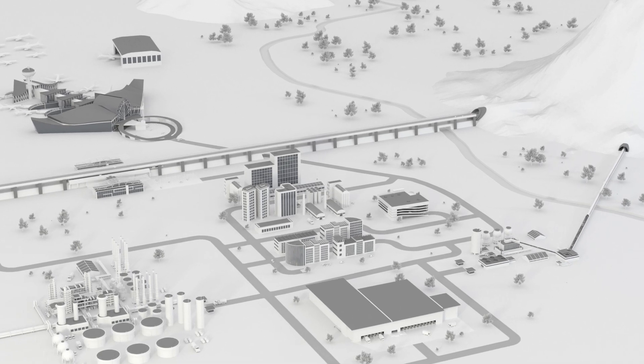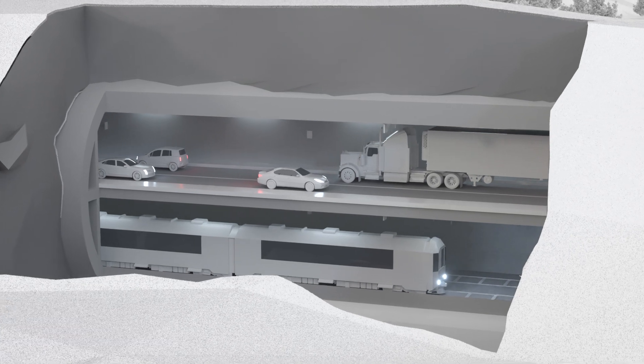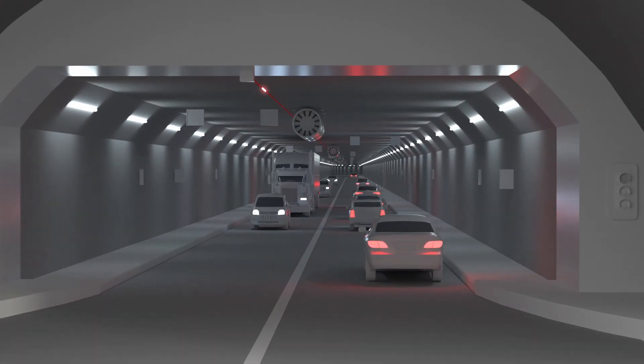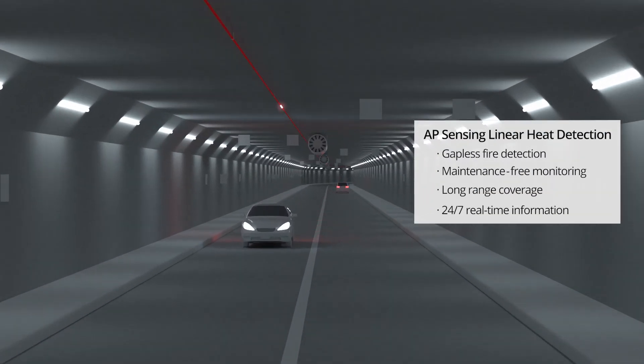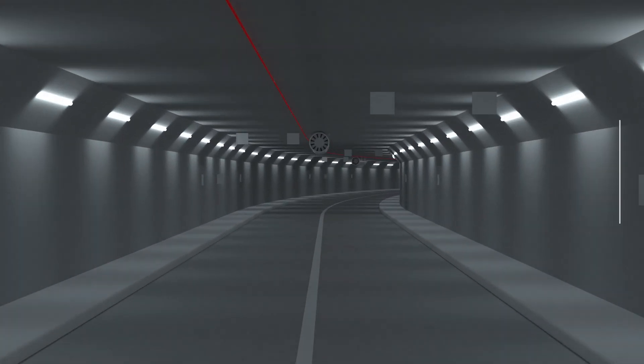Unlike traditional fire detection systems, our fiber optic linear heat detection system, LHD, continuously and actively monitors the real-time temperature at every point along an asset, precisely detecting and locating hotspots or fires within a few meters.